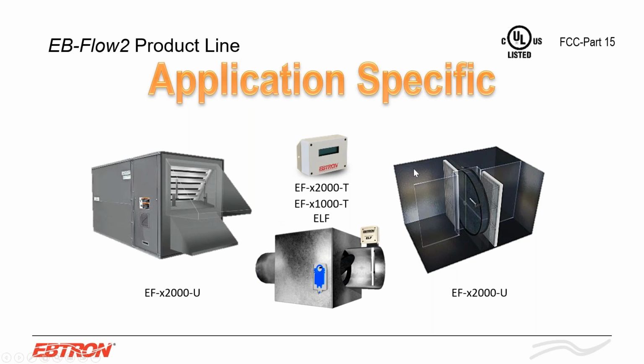So these are really designed for VAV box applications. See these in a lot of retrofit applications where they're pulling the crossflow rings out and they're installing these. It makes it really a high performance VAV box, again, because these can match your turn down requirements. We have the 2000T just has a display, and the 1000T is just stripped down, no display, but again, plus or minus 3% accuracy. For small rooftop package units, we have the U series right here, and we can also do smaller ERV measurement as well, where we are trying to maintain a pressurization differential between the intake and the exhaust side, right? So both of these probes are going back to this transmitter.